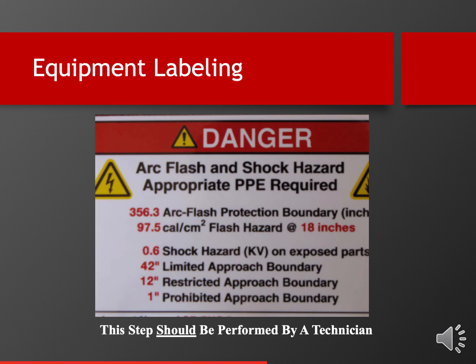And here we see the calculated incident energy at 97.5 calories and the various approach boundaries that those of you who have had the NFPA 70E training know. Now the one that went away is the prohibited approach boundary. That no longer exists. But this is an example of a slide that has all of the required elements you'd have in the 70E labeling requirements.